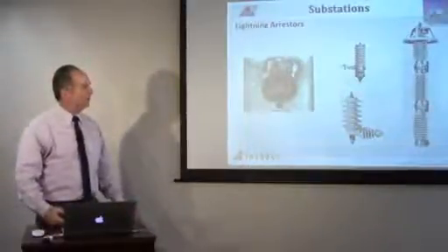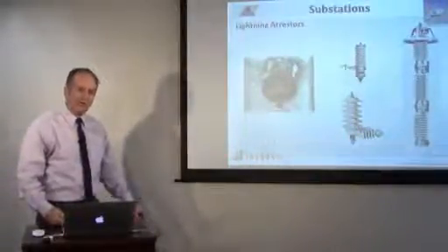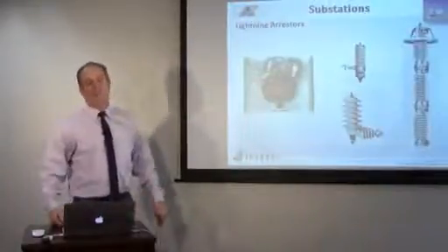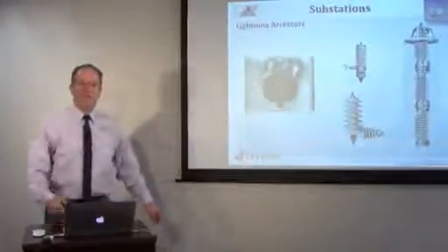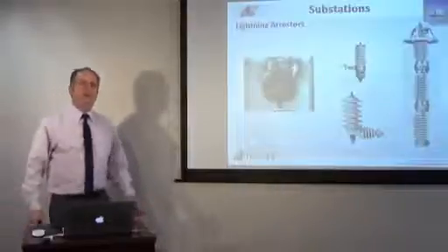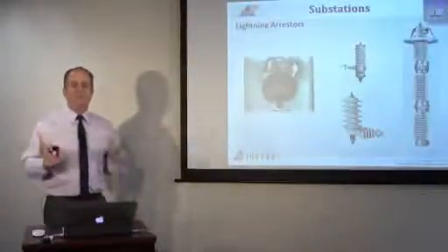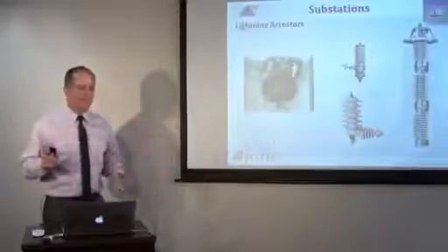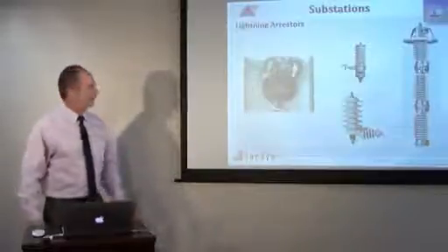And they're the ones that are supposed to operate first before a line burns down or the voltage gets so high on a transient from a lightning strike that it damages a transformer. That's why you'll see lightning arrestors on both sides of a transformer, common, just to protect that expensive transformer.